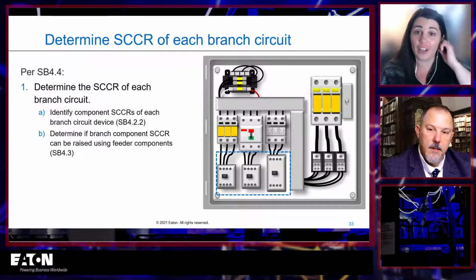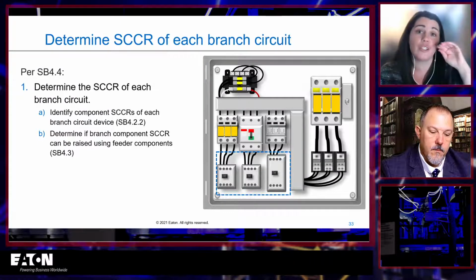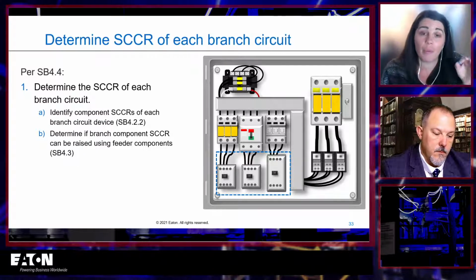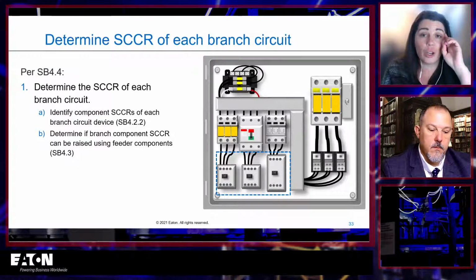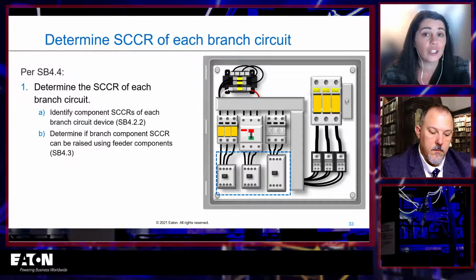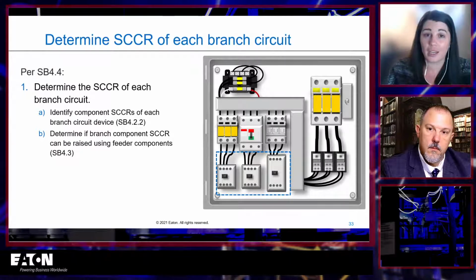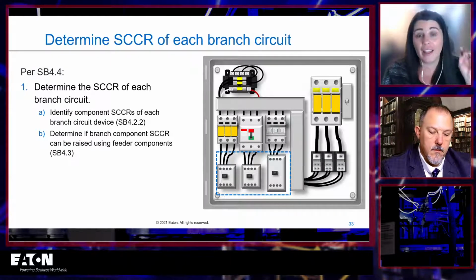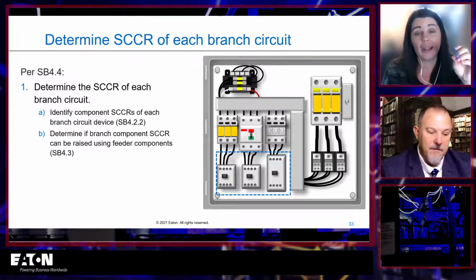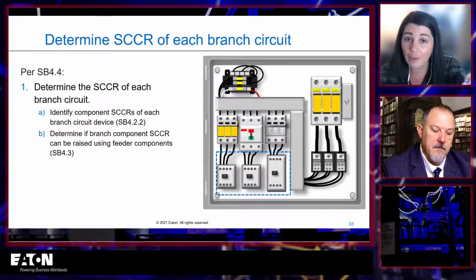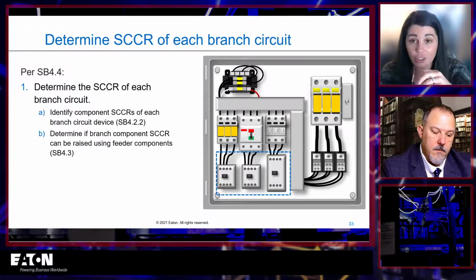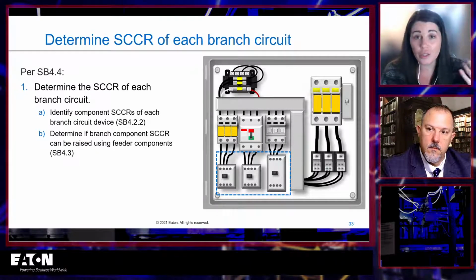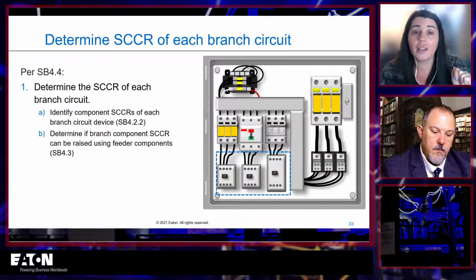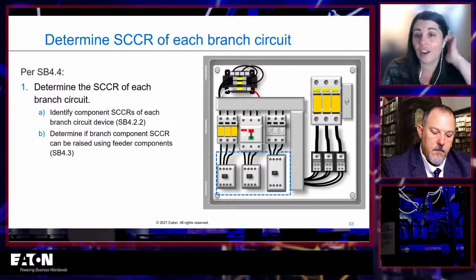You actually have to verify specific let-throughs of that device. You have to compare it to the devices below. And probably the most important thing is that you can only use this to raise component short circuit current ratings. You cannot use it to raise interrupting ratings. So if you have a very current limiting fuse in the main, but you have a 10 kA breaker in your branch, you can't use that fuse to raise the interrupting rating of that breaker, even if that fuse let-through is less than 10 kA. So it's very, very commonly misapplied.